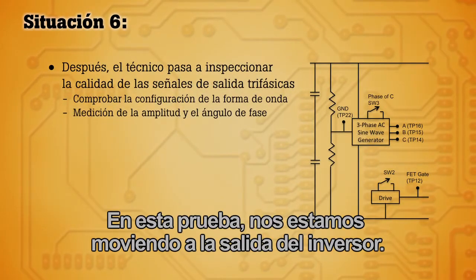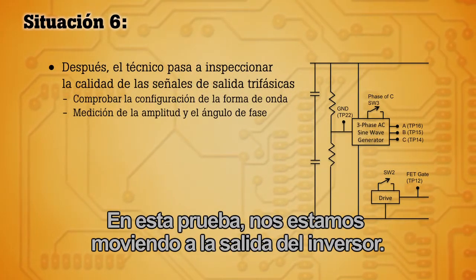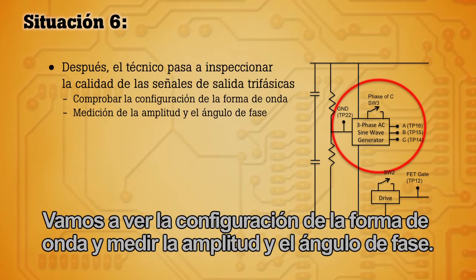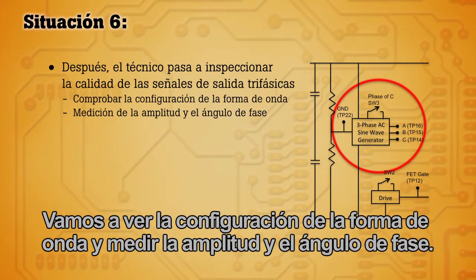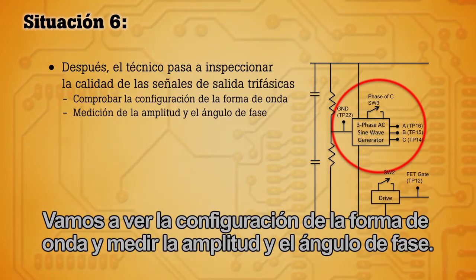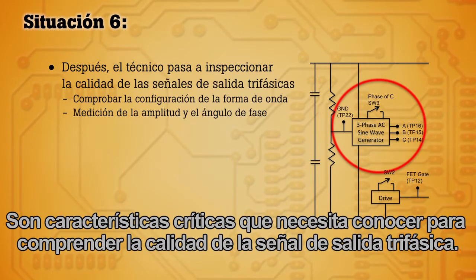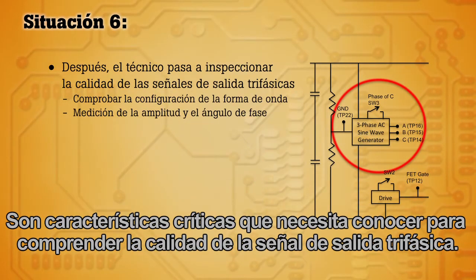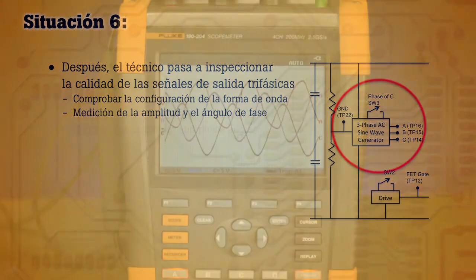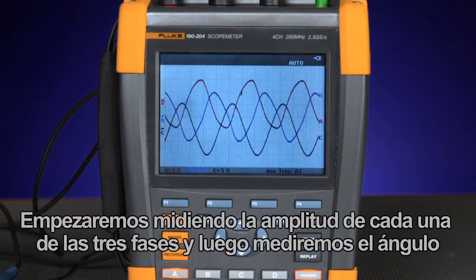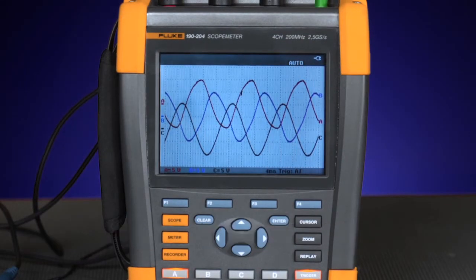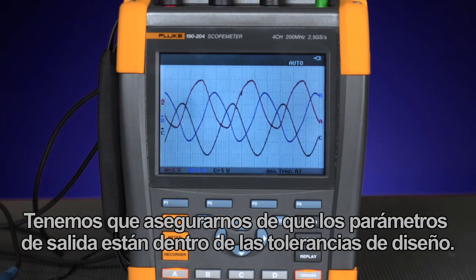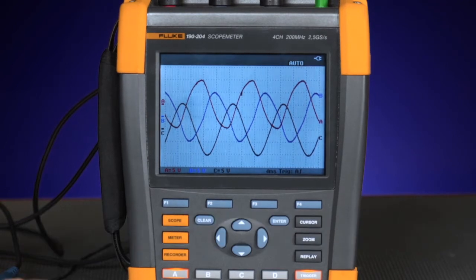For this test we're moving to the output of the inverter. We're going to look at the waveform shape and measure the amplitude and the phase angle. These are critical characteristics you need to know to understand the quality of the three-phase output signal. We'll begin by measuring the amplitude of each of the three phases and then we'll measure the phase angle between two of the phases. We need to make sure that the output parameters are within the design tolerances.